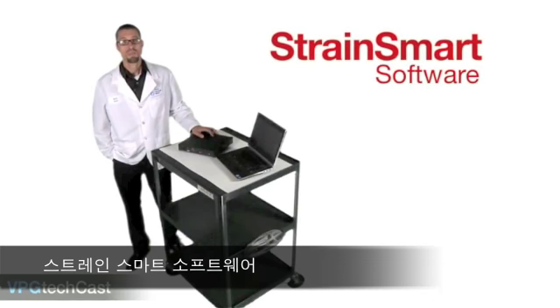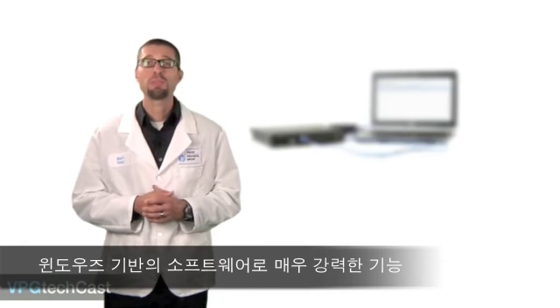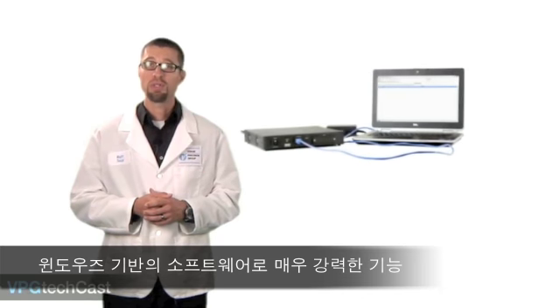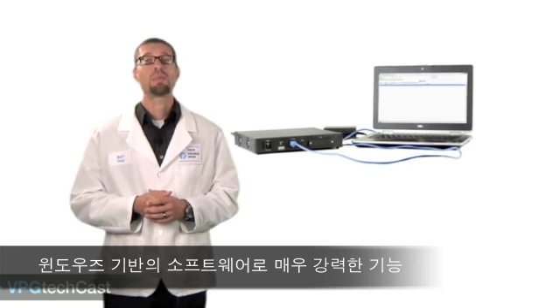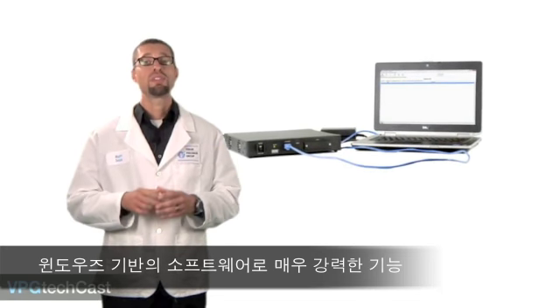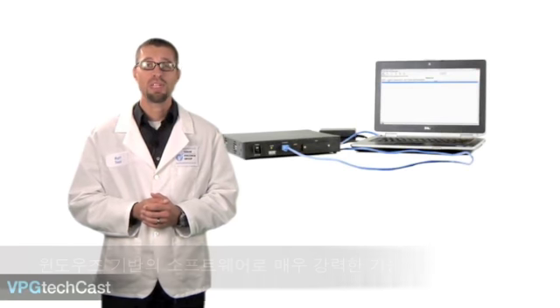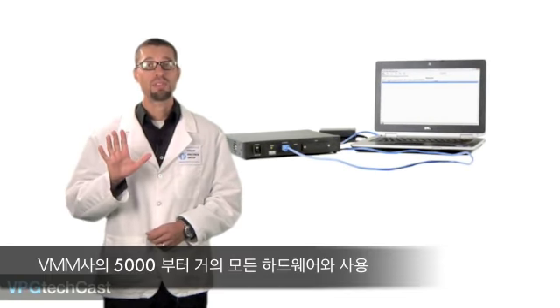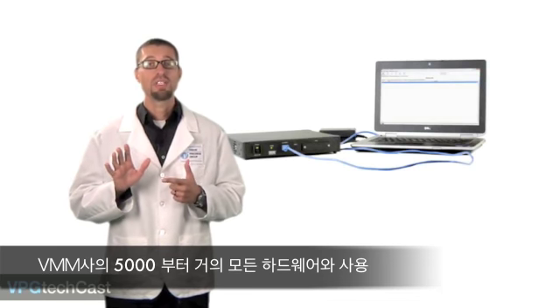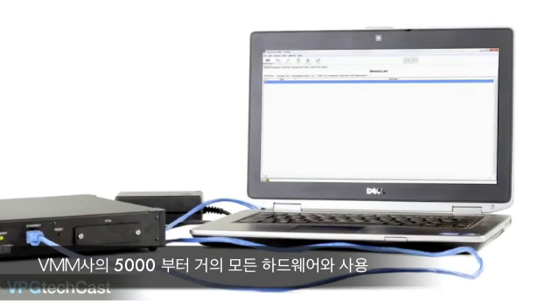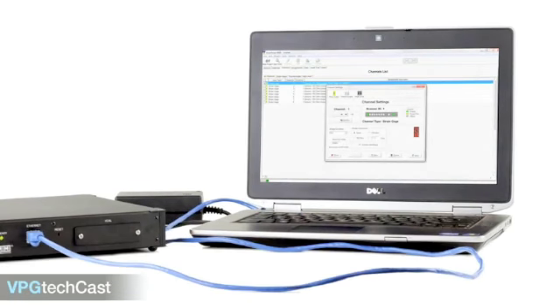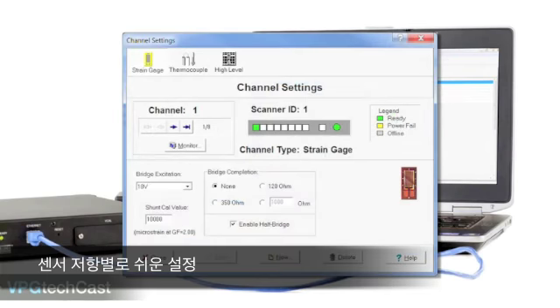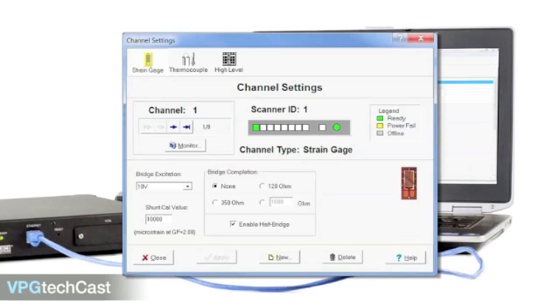Now let's take a look at the StrainSmart software. The StrainSmart software is a ready-to-use Windows-based software system for acquiring, reducing, presenting, and storing measurement data from a variety of sensors. It is designed to function seamlessly with a variety of Micro-Measurements instrumentation hardware, including our System 5000, 6000, 7000, and now 8000. Some of the key features that are common among the StrainSmart data systems are bridge completion provided through the 120, 350, or 1000 ohm internal precision resistors for quarter and half bridge setups. You don't have to provide external precision resistors.